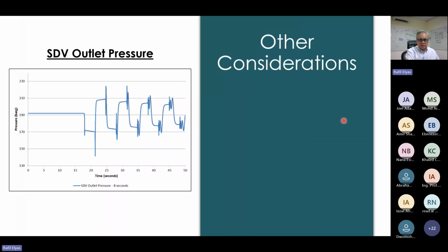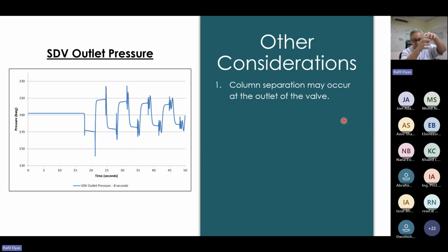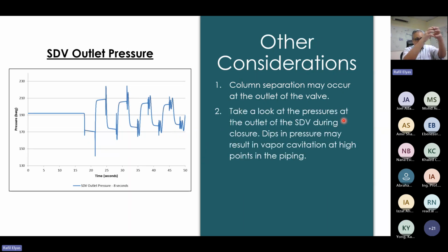So what are some of the other considerations? Sometimes, particularly if you've got overboard dump valves, which we see in a lot of the offshore facilities, as the liquid starts to go to the overboard dump, you might get the liquid separating because of the siphoning effect. The siphoning effect might essentially cause vapor pockets to occur, and that could also result in vapor cavitation on some of the overboard dump valves. I've got a lot of friends who sell valves for a living, and this is something they're always complaining about, the cavitation on the overboard dump valves.